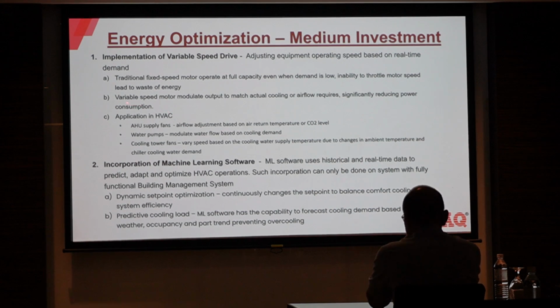And then VSD also modulates the output to match the actual cooling and airflow required. So this actually helps to significantly reduce the power consumption. And for VSD, the speed to the power consumption is in the factor of cube. So whatever you save is in the cubes. So when you throttle even 1 or 2 Hertz or 5%, it actually brings significant savings.